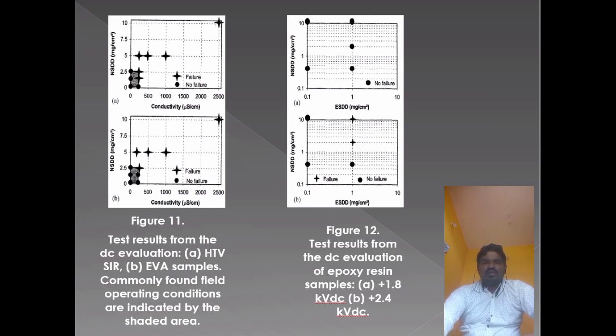a much poorer electrical performance of the polymers, which is evident from the results presented in figures 10A and 10B. Sample failures occurred not only at high pollution levels but also under pollution conditions likely to be found in a large number of locations worldwide. This is of major practical importance, since failure of these polymers would be anticipated at electrical stresses in a range close to that commonly used for non-ceramic outdoor insulating devices selected for DC applications. Next will be epoxy resin samples.